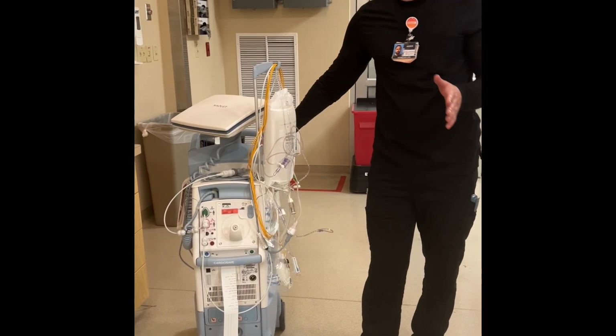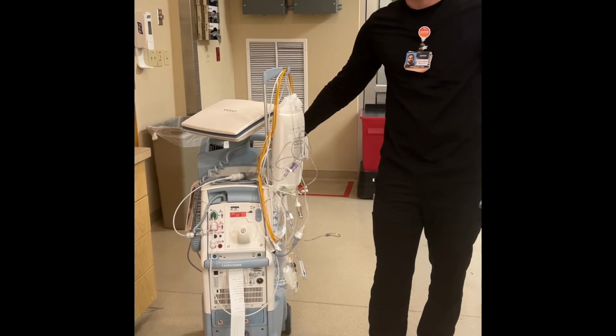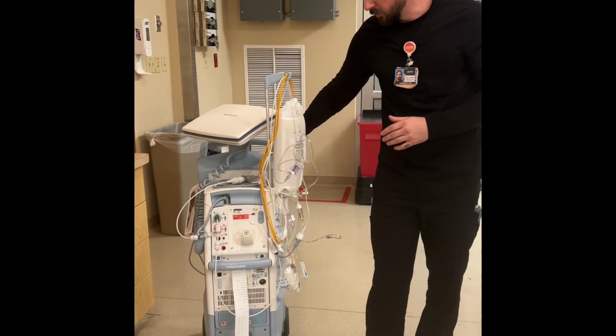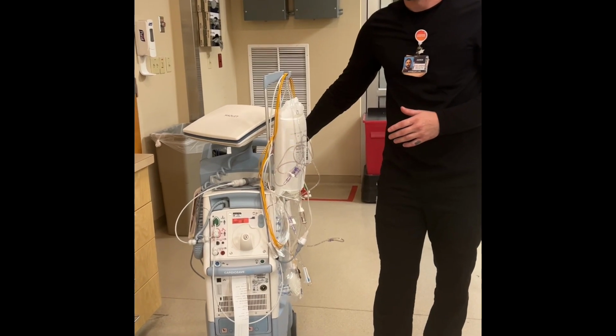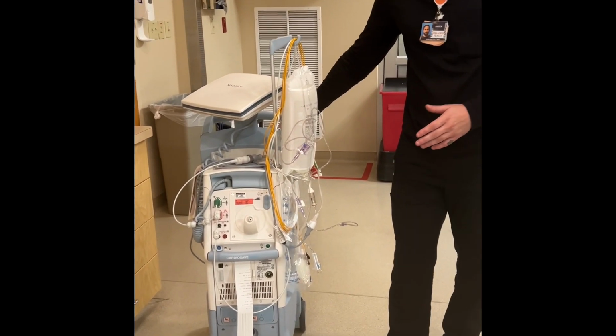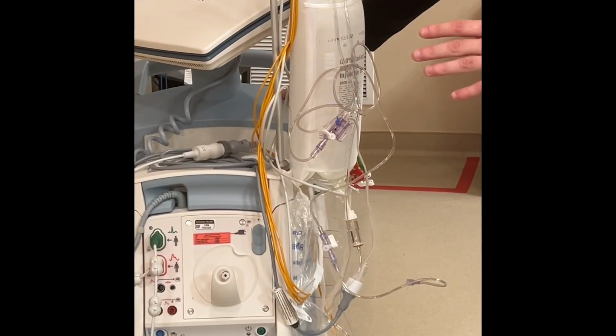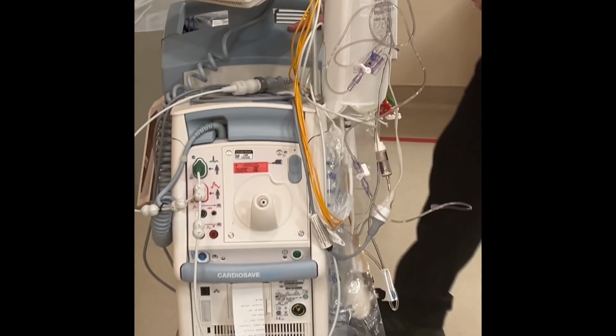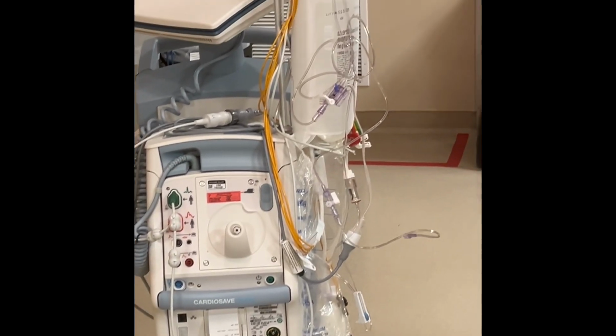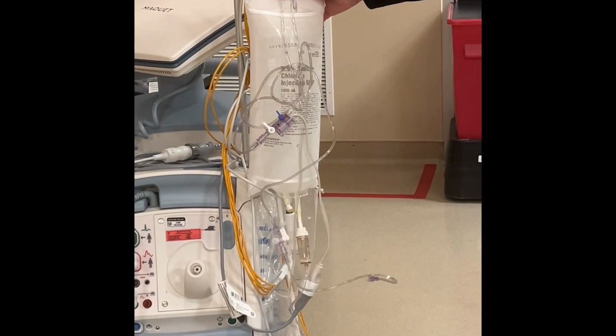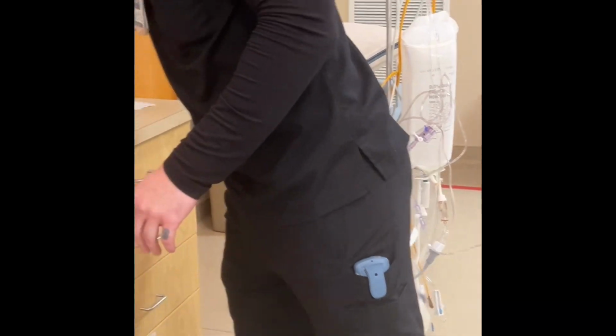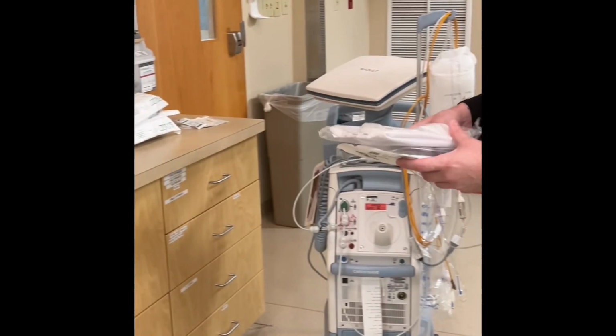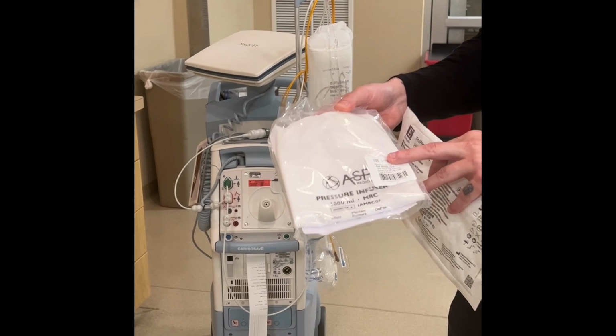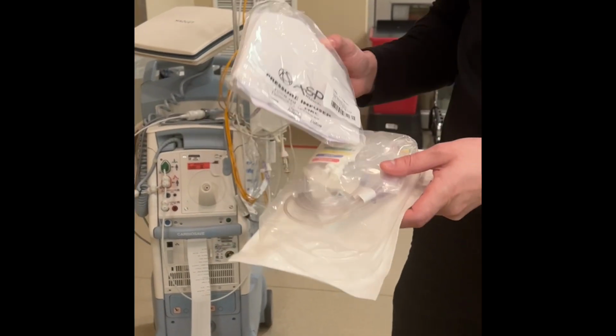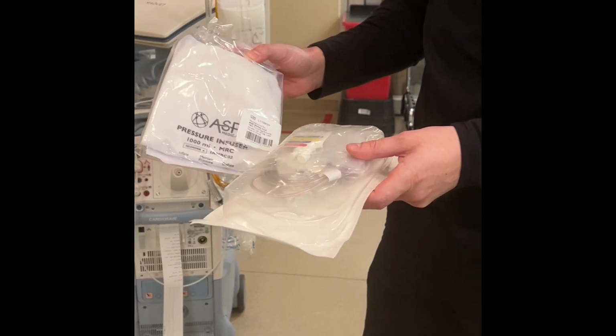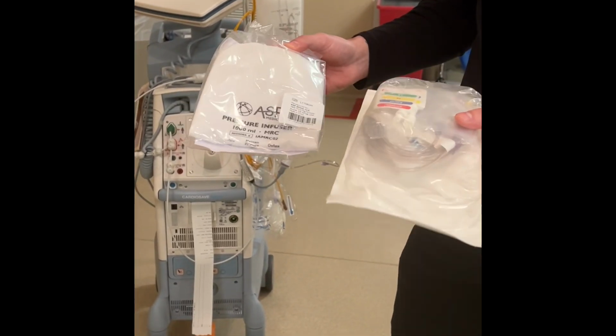So you're already going to be up here, the patient's already going to be draped, they're already going to be working on the patient. So what you want to do before they're even calling for it is taking a look at the machine to make sure you have everything you need. First, you want to check that you have your setup for your pressure tubing, and it is simply 1,000 cc normal saline, 1,000 pressure bag, and your pressure tubing itself. This is exactly like an A-line. The only difference is that it doesn't have a vamp.